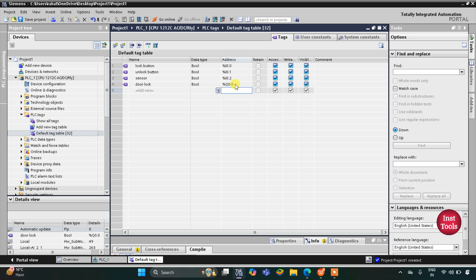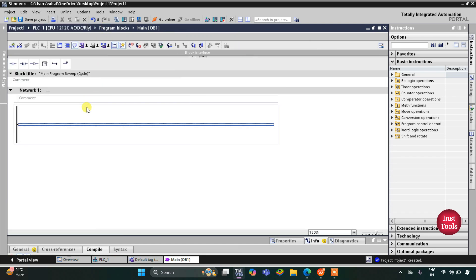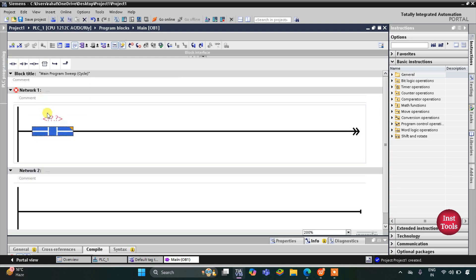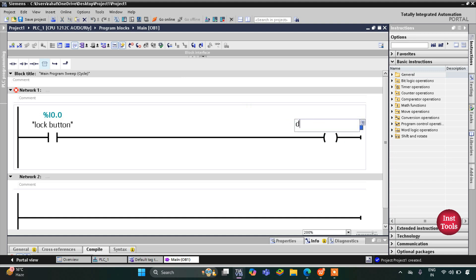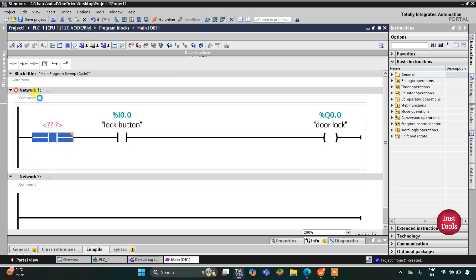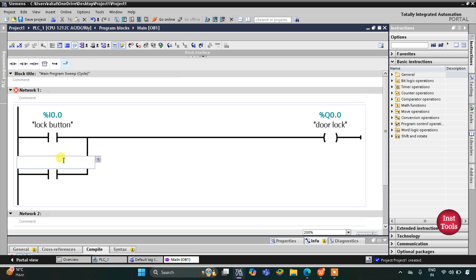After adding our inputs and outputs, we will go to program blocks and then main OB1. Here we will be drawing the ladder diagram. First I will insert a normally open contact for the lock button, and then I will insert a coil for door lock. When the lock button is pressed and released the door should be locked, so I will open a branch, add a normally open contact, and close it. This will be door lock — the latch contact.